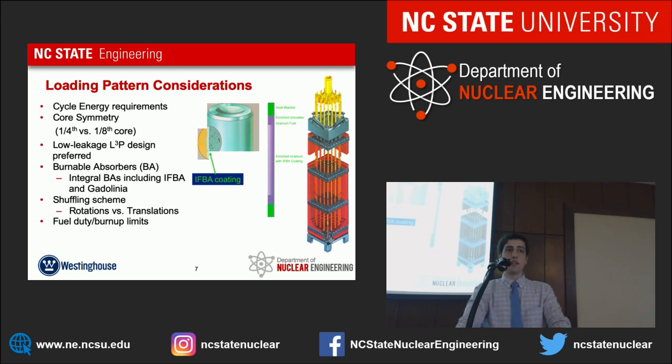We're designing a low leakage pattern, going through an L3P low leakage pattern with our most burnt fuel towards the periphery, as you'll see in our designs, and all of our fresh fuel towards the center. We make sure the burnt fuel's at the periphery to minimize neutron leakage, maximize economy, and minimize unnecessary radiation of the reactor pressure vessel.